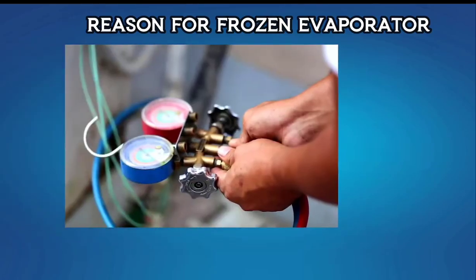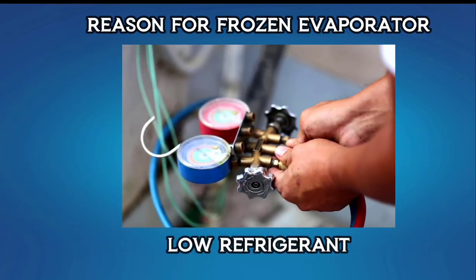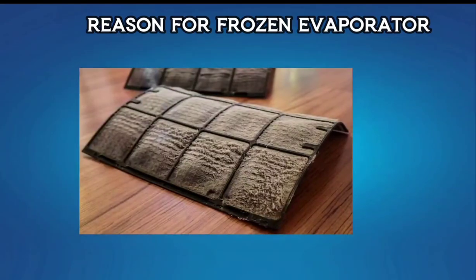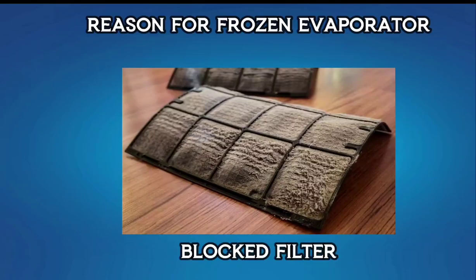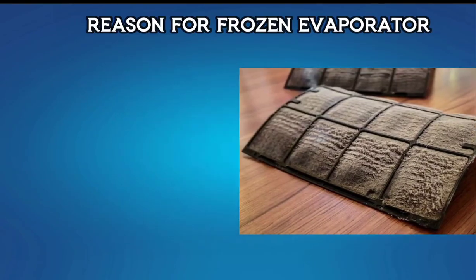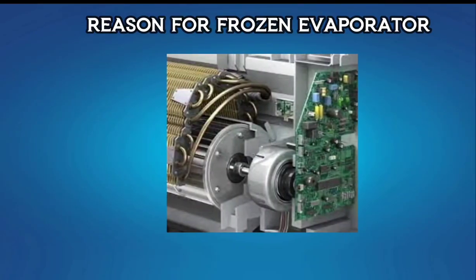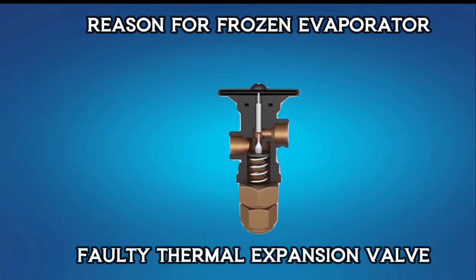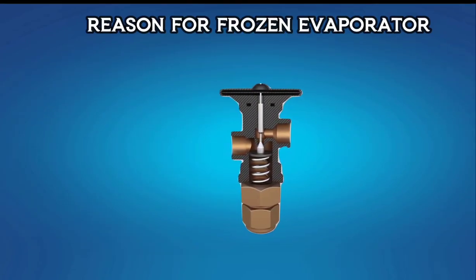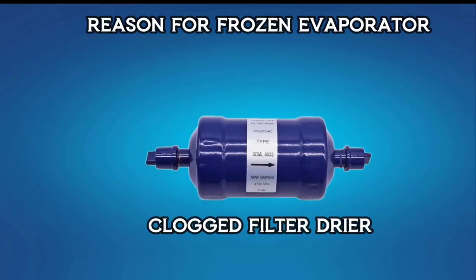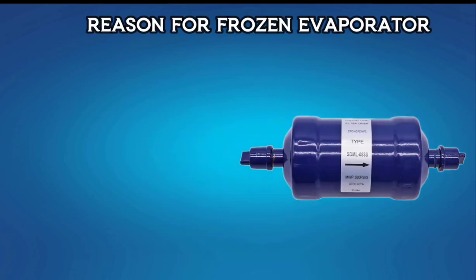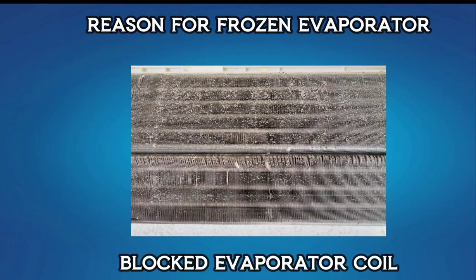The first important reason is low refrigerant. This problem may occur because the entire filter is blocked. The blower fan in the indoor unit may not work. The thermal expansion valve may not be working properly. It could be a filter dryer or evaporator coil block. These are all causes of evaporator coil freezing.